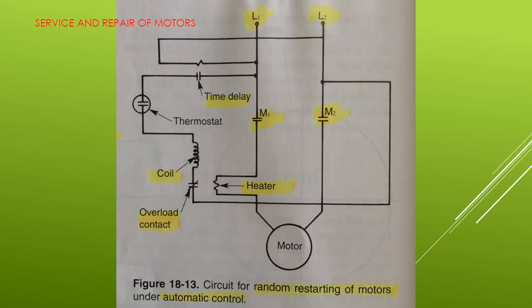Service and repair of motors. Generally, motors should not be allowed to restart automatically after a loss of power. If automatic operation is necessary, provision should be made for random restarting to prevent the excessive voltage drop in the wiring that would occur if all motors came on at one time. This can be accomplished by including a low-cost time delay relay in the magnetic motor starter control, as shown in figure 18-13. This random restart feature is especially desirable for large horsepower motors.